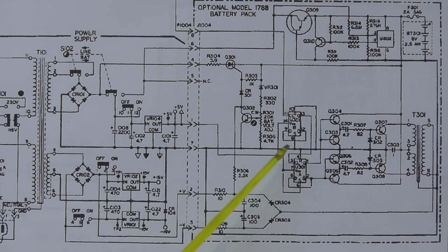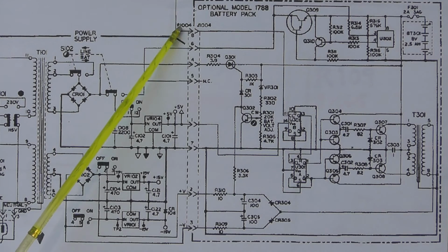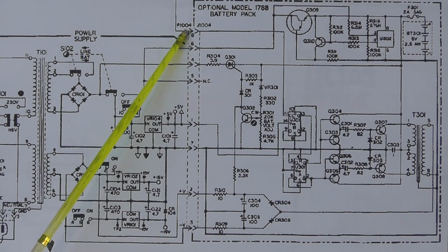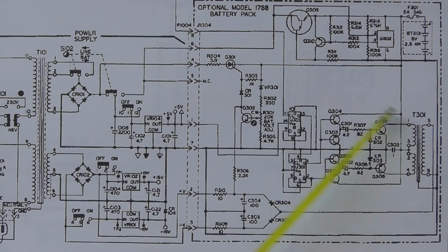The main difference to this circuit compared with some other inverters is that the signal sent to this D-type flip-flop is coming from the clock oscillator of the meter, which, if you remember, is 100 kilohertz. So the switching for the inverter is at 100 kilohertz, which is exactly the same frequency as what's used by the analog to digital converter and the logic circuits on the meter. And the reason they do this is that by synchronizing those two frequencies to be the same frequency, it removes the noise effects from the inverter affecting the overall performance of the meter.